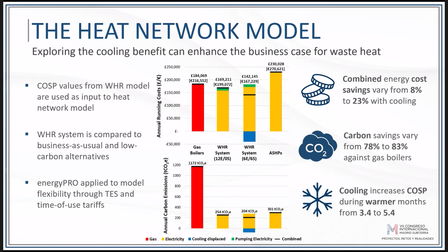Another way of looking at the cooling benefit is through the coefficient of system performance. If you look at the warmer months, from May to October, when the system would operate in supply mode, if it were operating only in extract, the COP would be 3.4. But by combining heating and cooling, operating in supply mode, the COP can increase to 5.4. So although you're reducing the heat pump efficiency in some sense, by combining the benefits of cooling and heating, your overall system efficiency can be much higher.